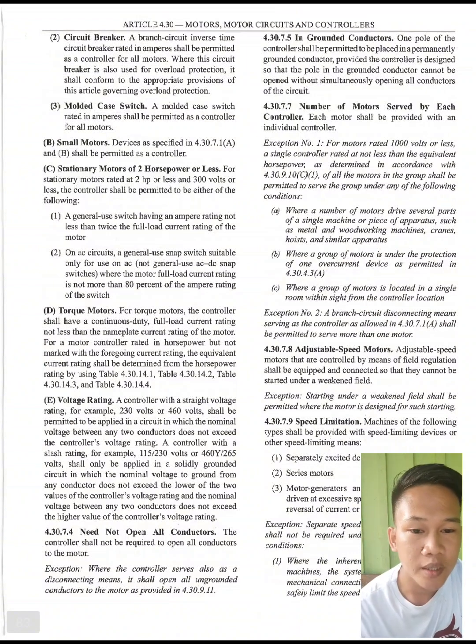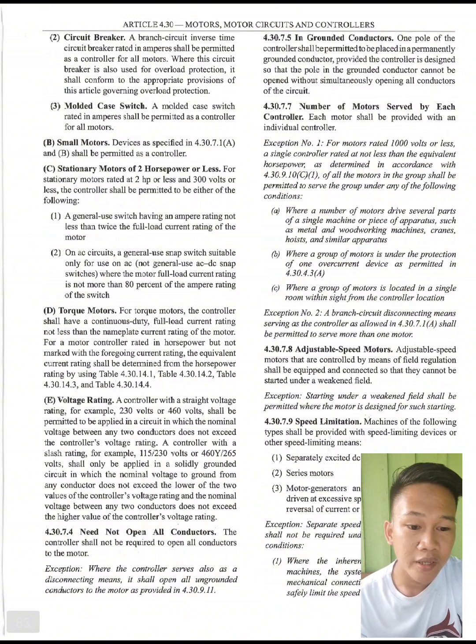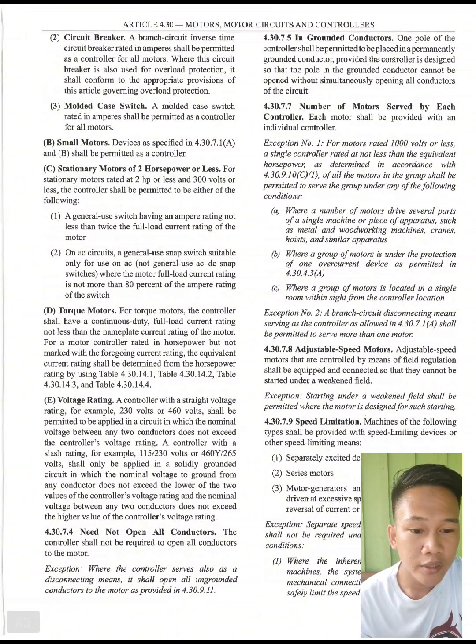So next is 4.30.7.7. Number of motors served by each controller. Each motor shall be provided with an individual controller. Exemption number 1. For motors rated 1000 volts or less, a single controller rated at not less than the equivalent horsepower, as determined in accordance with 4.30.9.10 C1 of all the motors in the group, shall be permitted to serve the group under any of the following conditions. First, where a number of motors drive several parts of a single machine or piece of apparatus, such as metal and woodworking machines, cranes, hoists, and similar apparatus.